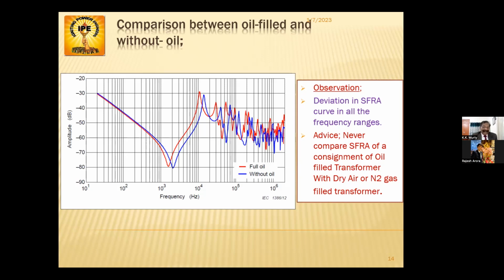In the OEM's works, they generally take the SFRA curve with the oil-filled transformer, and then they remove the oil and transport the transformer nitrogen filled or dry air filled. So in that case, the SFRA curve will have a difference. As you see, the red colored curve is with full oil, and the blue colored is without oil. Because the dielectric strength of oil and nitrogen or air is different, there is a difference in all the frequency ranges. So the observation is deviation in SFRA curve in all the frequency ranges. The basic advice: never compare the SFRA of an oil-filled transformer with a dry air or nitrogen filled transformer. This has to be taken care of, otherwise you will feel that there is a lot of problem with the transformer. No, it is not like that.